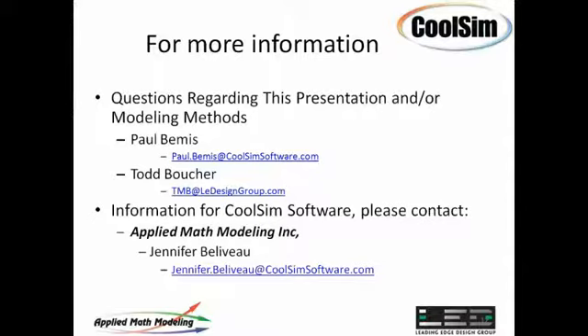Yeah, I would agree with that, Paul. And just to briefly add, there are a lot of moving parts to cooling units, so any part can fail, and that would cause a failure in the unit. At our organization, from an assessment perspective, we're asked a lot to look at an existing environment just like this, where the customer will say, we know on paper we have double or triple the cooling capacity we need based on the IT load, but when we lose a cooling unit, we lose the room. That's why utilizing a tool like this, and having the ability to do it on this project, was a great way to articulate to the customer exactly what was happening.